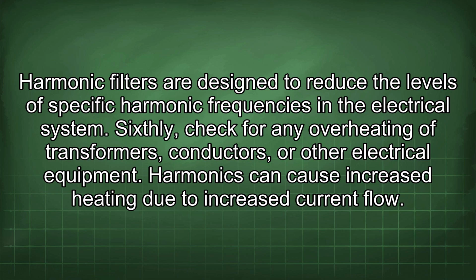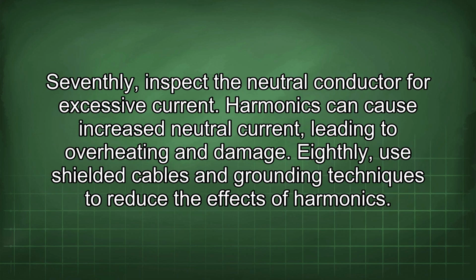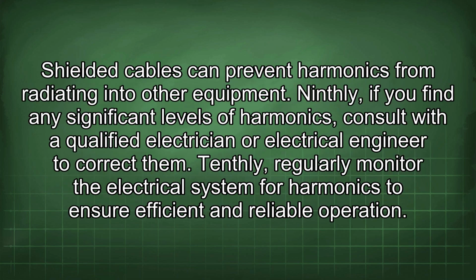Sixthly, check for any overheating of transformers, conductors, or other electrical equipment. Harmonics can cause increased heating due to increased current flow. Seventhly, inspect the neutral conductor for excessive current. Harmonics can cause increased neutral current, leading to overheating and damage. Eighthly, use shielded cables and grounding techniques to reduce the effects of harmonics. Shielded cables can prevent harmonics from radiating into other equipment.